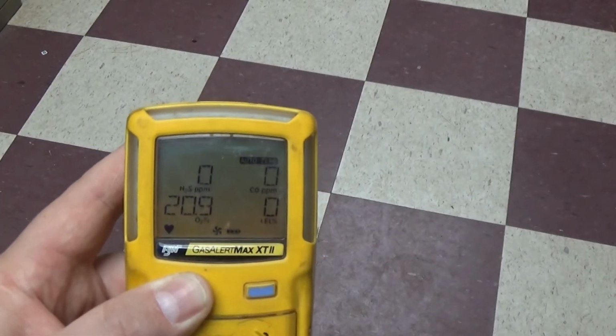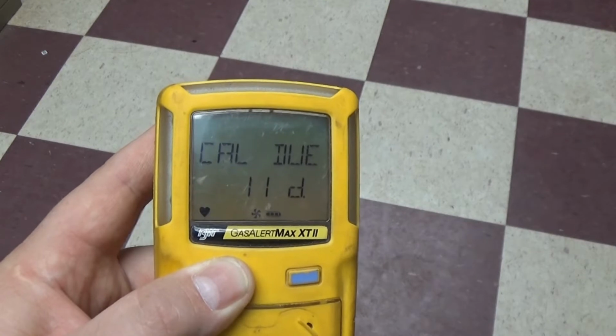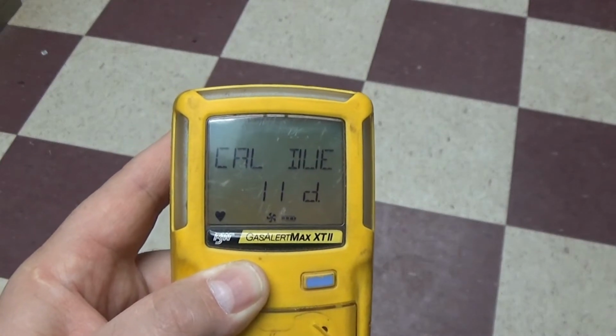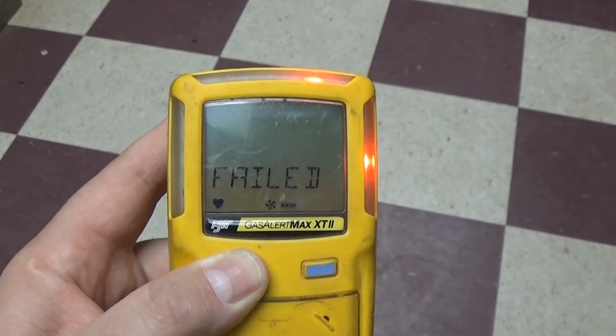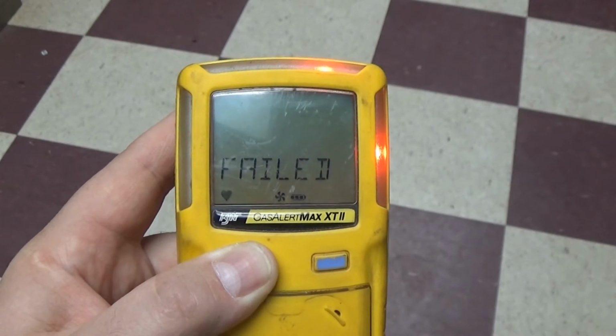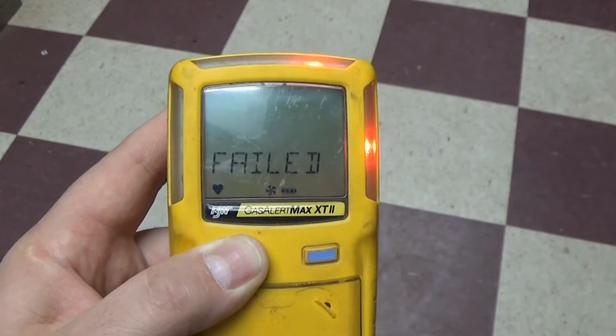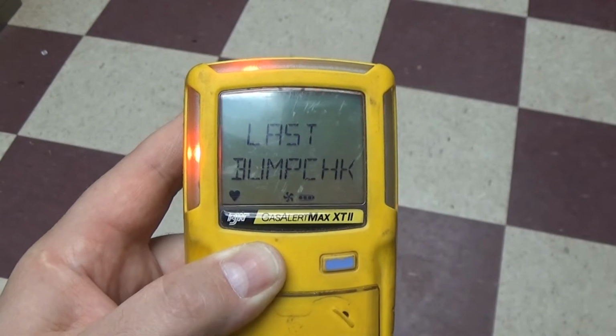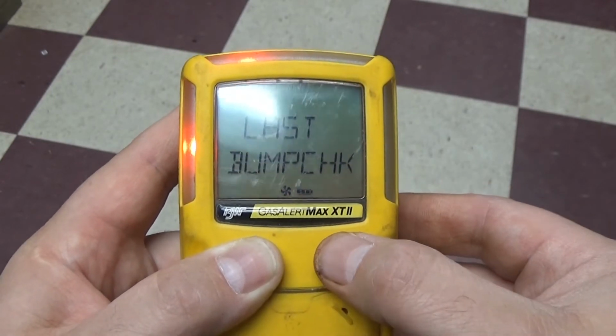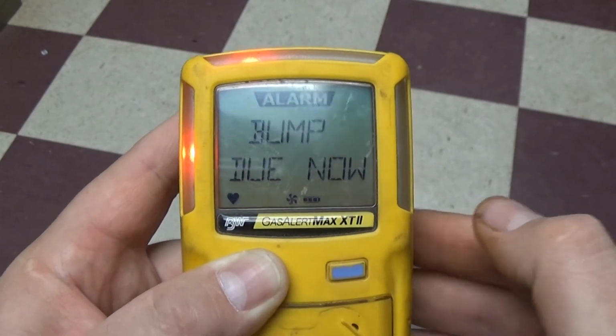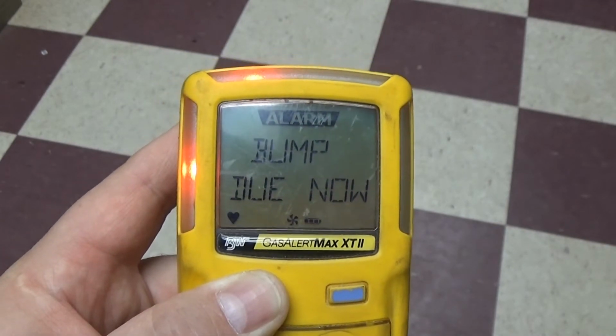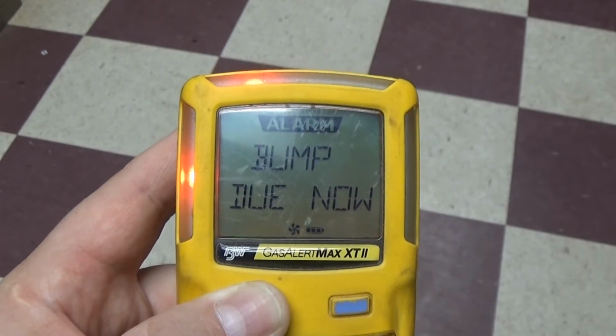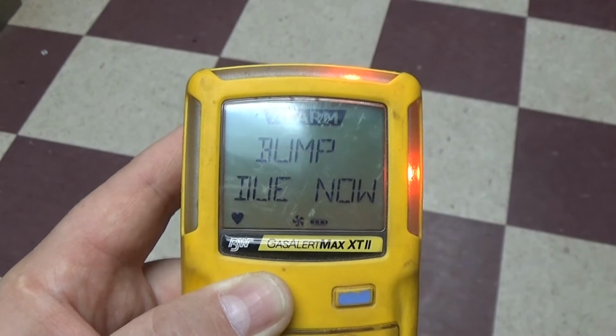One of the biggest problems we've seen when employees ask us to work on the meter is this alarm that it shows right here, last bump failed, or last bump check failed. Before you can put it back into the cradle to bump again, you've got to hit the blue button one time, and then it'll tell you bump due now. After that's showing, you can place it back into the cradle and bump it again.